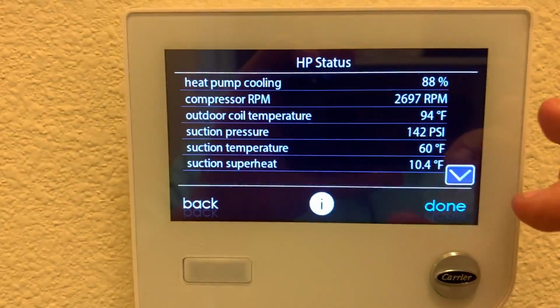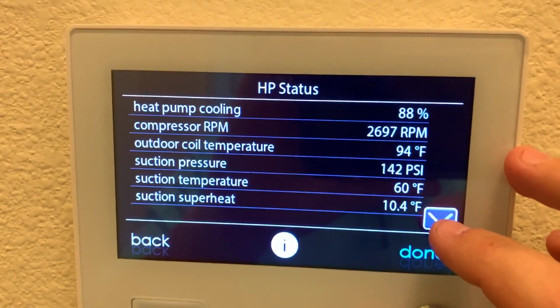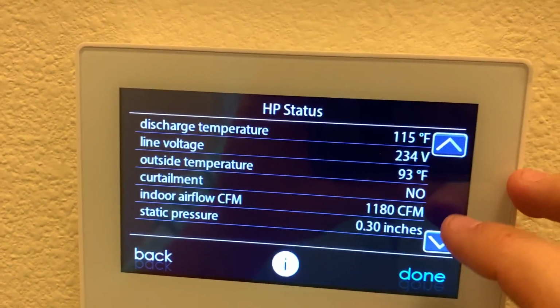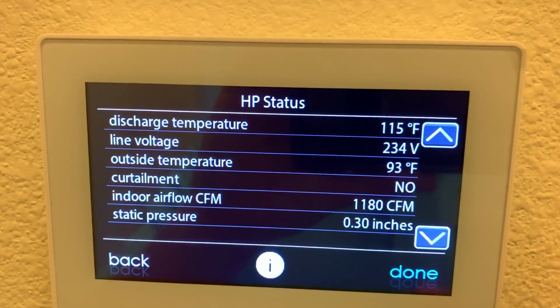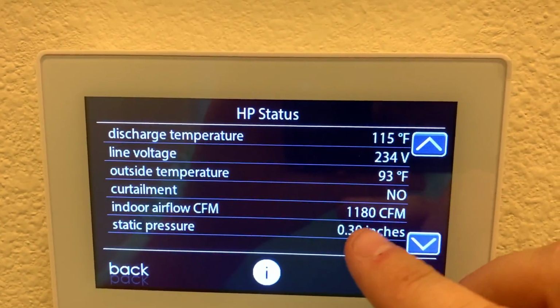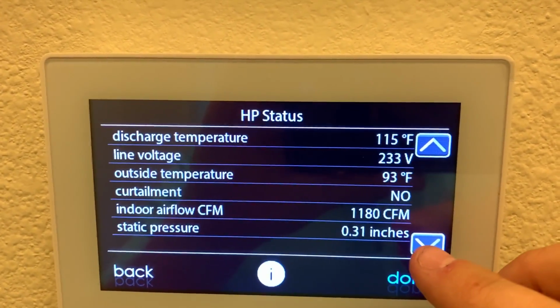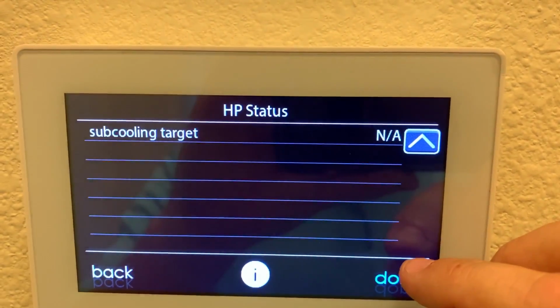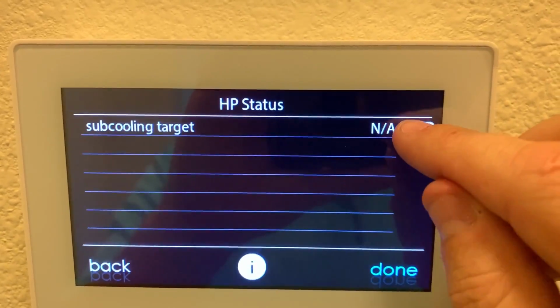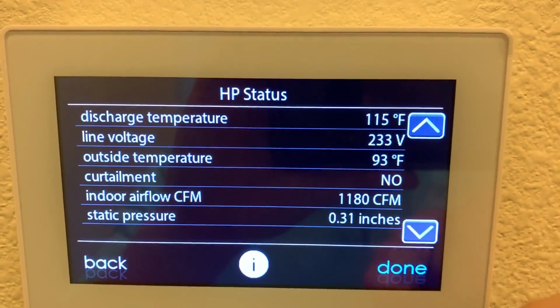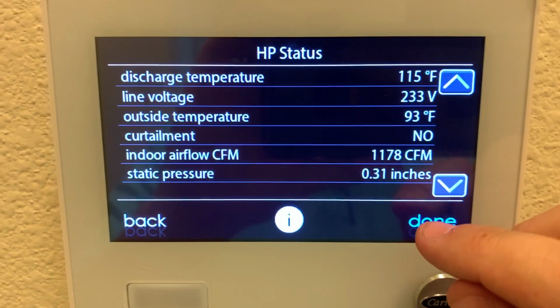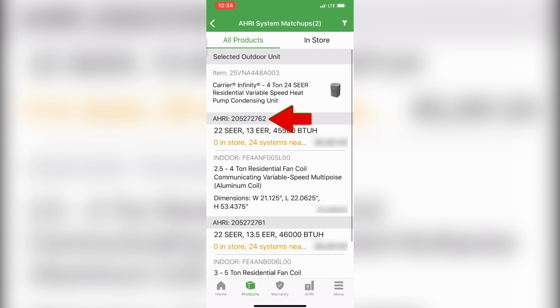All right, we get some additional information off of the display here. Shows us superheat, line voltage, static pressure. We're really good on static pressure, even at our 1180 CFM on this. Yep, everything is looking good now. We did all of our tests, did our Measure Quick report, and we also checked it outside with the Bluetooth connection to the condenser. So this matches this AHRI number that you see up top here, 205272762.